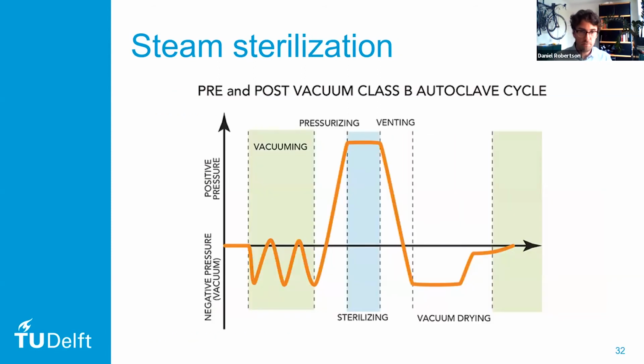Now, this is what a typical sterilization cycle of an autoclave looks like. We have the steam pressure on the y-axis, and we have the time on the x-axis. What happens is that you close the autoclave door, and it pulls through a few vacuum cycles. These cycles pull all of the air out of the autoclave, and this air that's sucked out is replaced by steam. Replacing it by steam means that the temperature will rise much more quickly to ensure more quick sterilization.